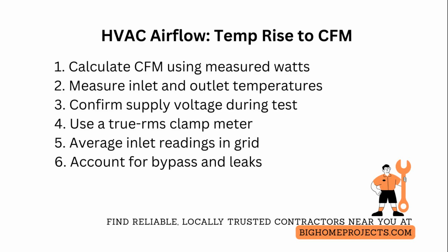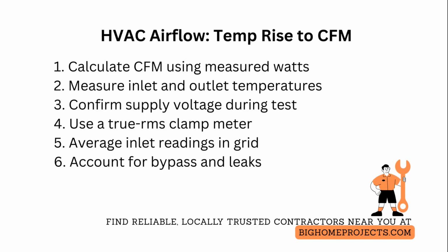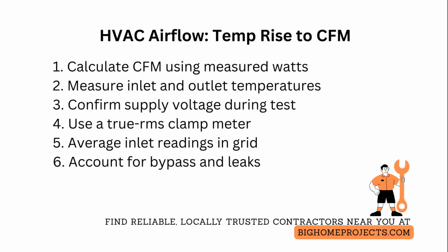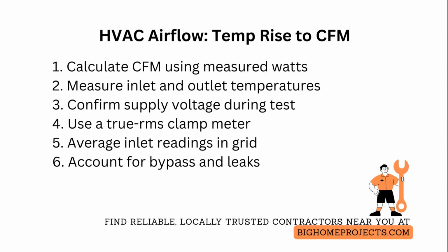estimates. Next, measure temperature rise using two digital thermometers placed as close to the inlet and outlet of the heater as possible, averaging multiple steady readings after the system has run at steady state for at least 5 minutes. Third, if the system uses single-phase power, measure supply voltage at the heater during the test, because voltage sag will change wattage and thus cubic feet per minute calculations.